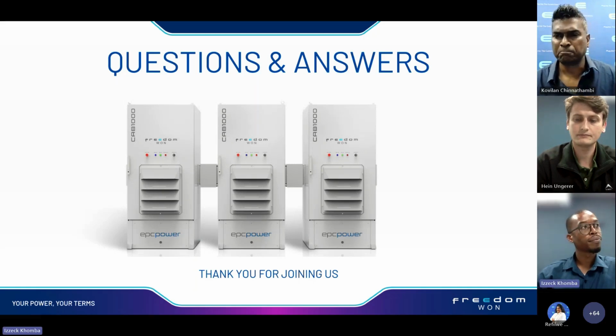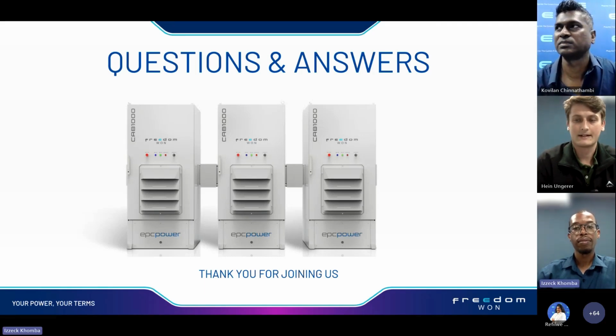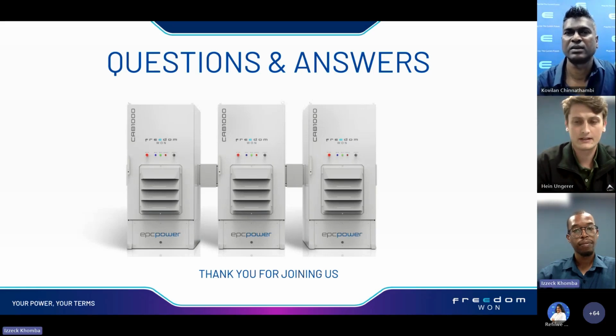Thanks, Isaac. We've got one more question from Repower. What are the inverter capabilities with inductive loads in an off-grid scenario? I'll take this one. So the inverter obviously has full reactive power generation capabilities, so it can supply any inductive load. The only caveat here is that during the transient stage when the load is started up, the bus voltage will drop depending on how big the inductive load is. But the inverter won't trip out. It will just bring the bus voltage back up once the reactive power has been consumed by the load.